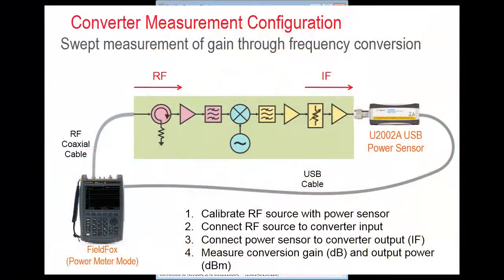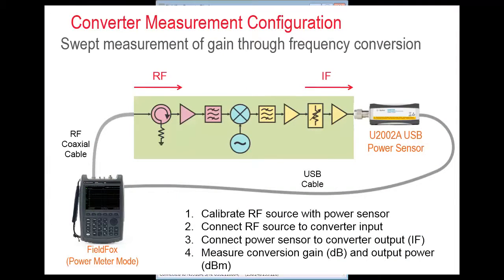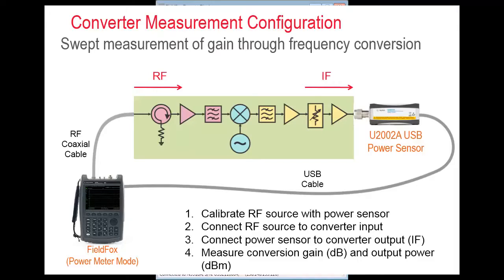Basically, there are four steps to making a frequency converter measurement with Option 208. One, calibrate the RF source for level input signal power with the USB power sensor. Two, connect the RF source to the frequency converter's input port. Three, connect the power sensor to the frequency converter's output port. And four, measure conversion gain, or loss, expressed as a negative gain.